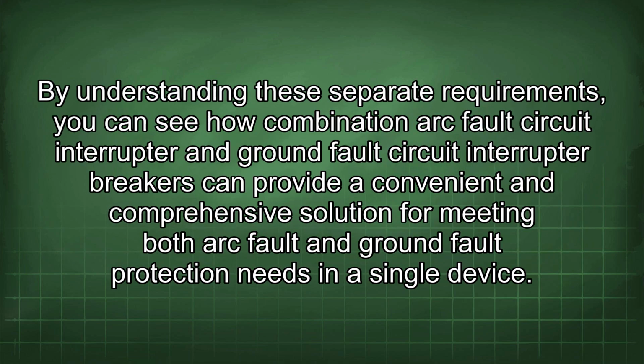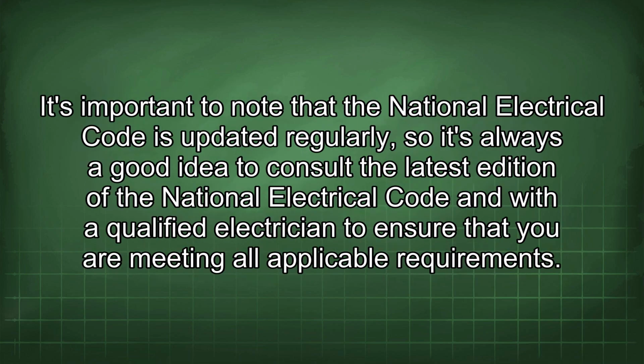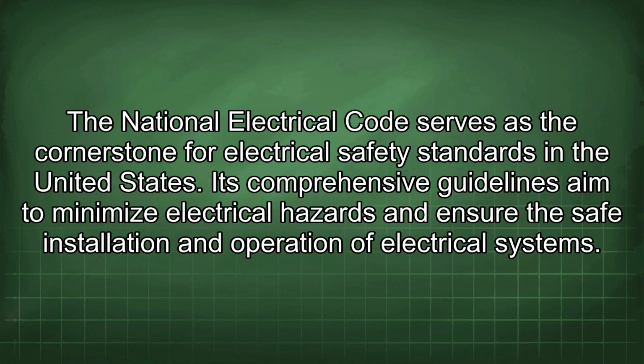By understanding these separate requirements, you can see how combination arc fault circuit interrupter and ground fault circuit interrupter breakers can provide a convenient and comprehensive solution for meeting both arc fault and ground fault protection needs in a single device. It's important to note that the National Electrical Code is updated regularly, so it's always a good idea to consult the latest edition of the National Electrical Code and with a qualified electrician to ensure that you are meeting all applicable requirements. The National Electrical Code serves as the cornerstone for electrical safety standards in the United States.